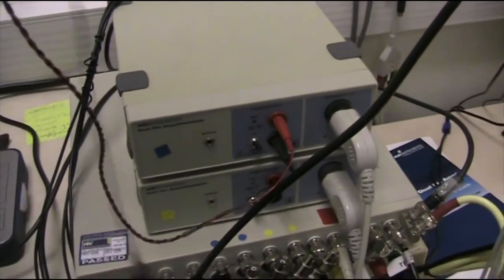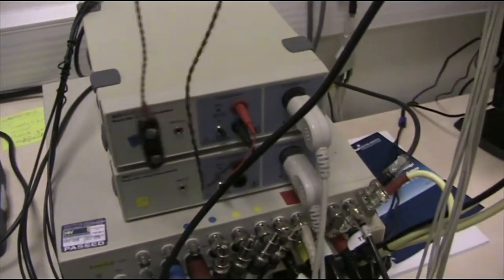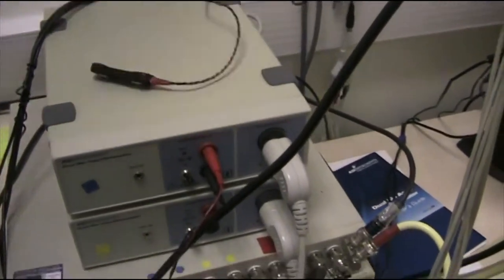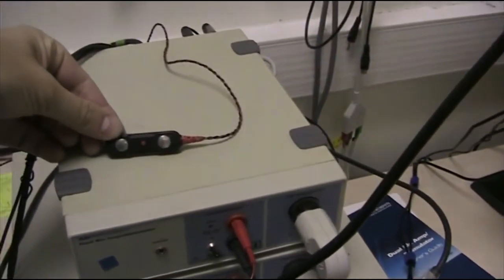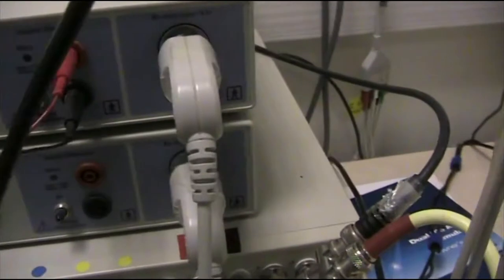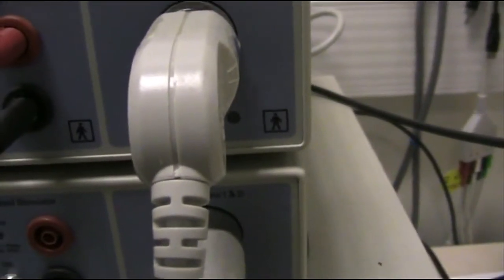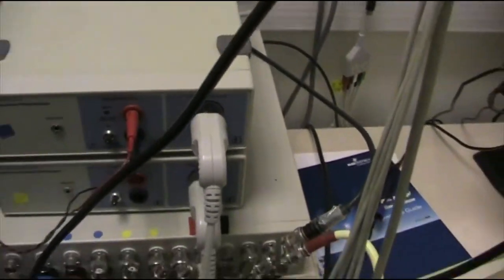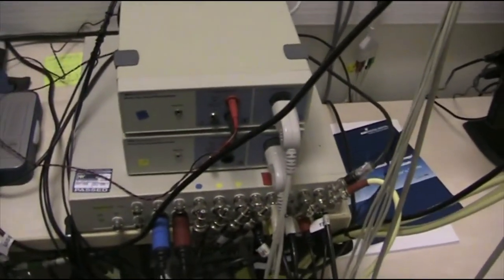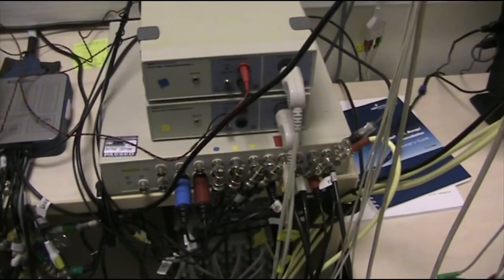There's also a stimulator cable, which allows you to stimulate people's nerves and muscles electrically. This is safe to put on humans, as shown by the little human sign. And that means that the electrical stimulus is isolated from the mains electricity.